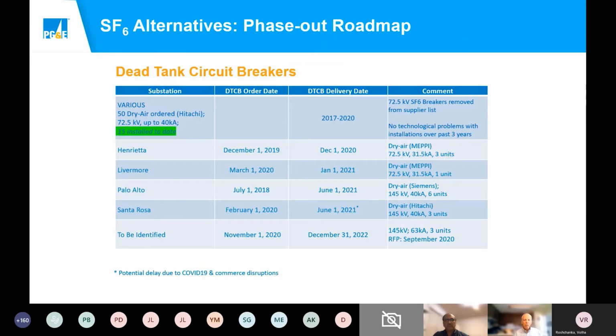So this is our roadmap in phasing out SF6, and this particular slide looks at dead tank circuit breakers. I want to focus on just the last two columns, the delivery date and the comments. On the first line, we've been buying 72 kV breakers from Hitachi for about 3 years now, so we consider those a commercial product that's gone beyond the pilot stage - that's our standard now for that class of breaker.